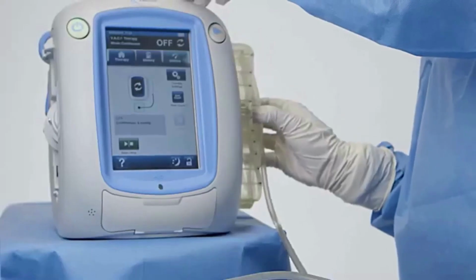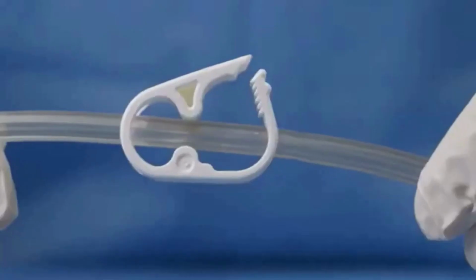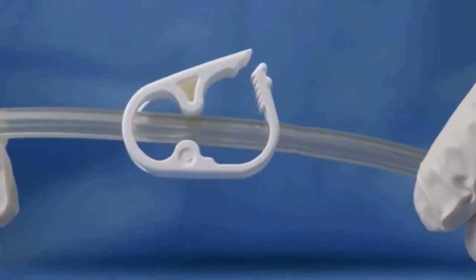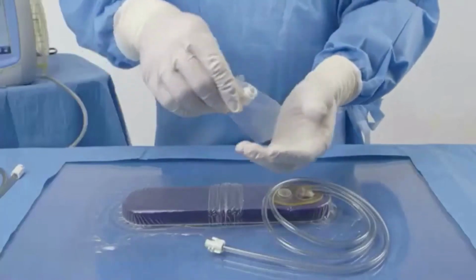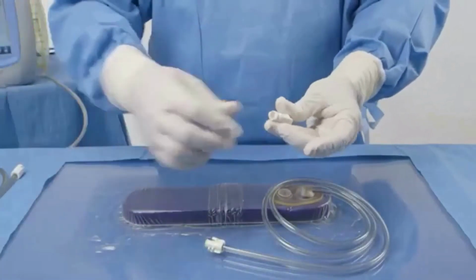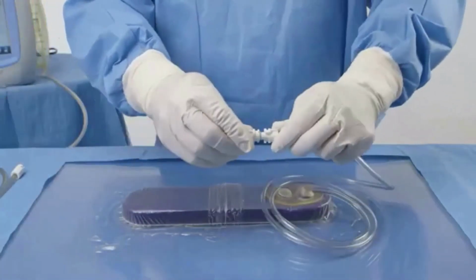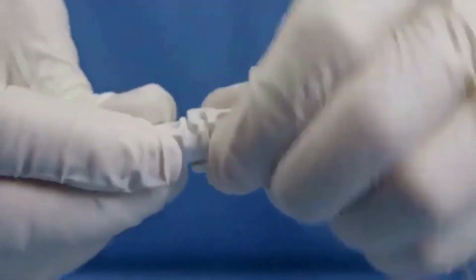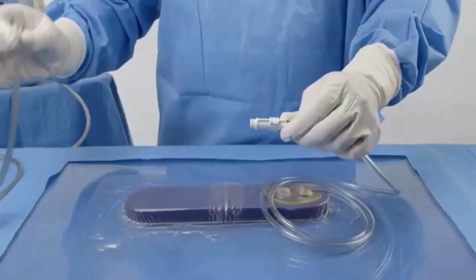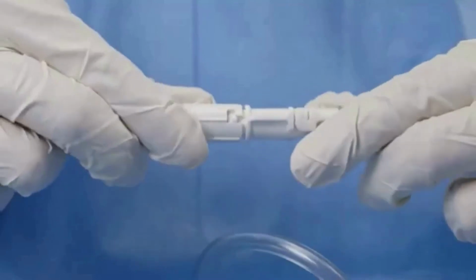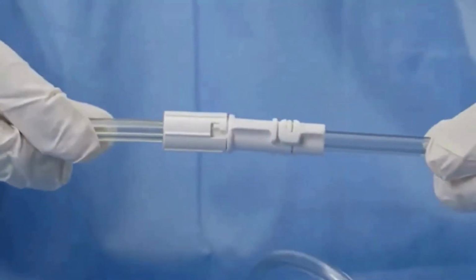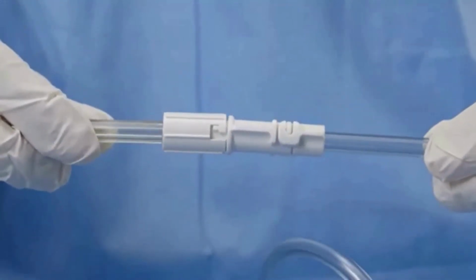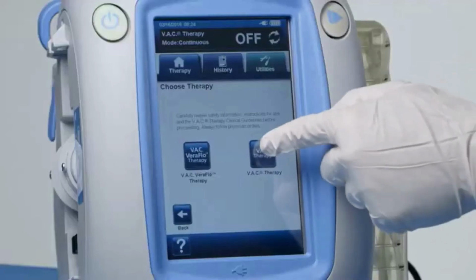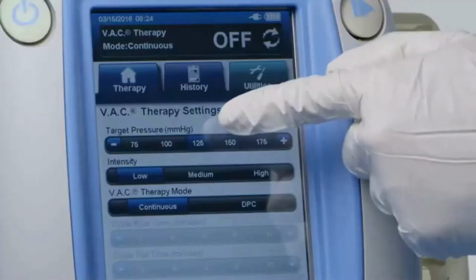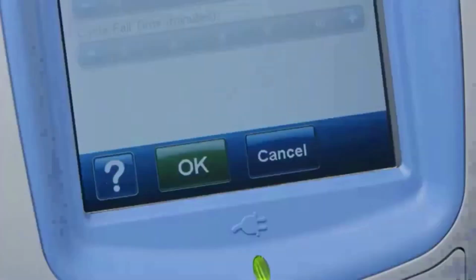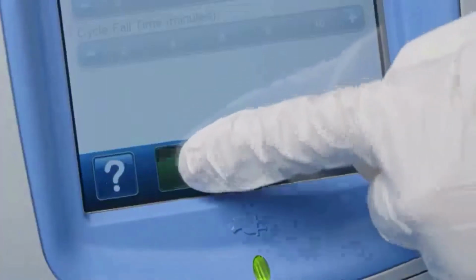Insert and secure the canister into the VAC therapy unit and ensure the clamp on the canister tubing is open. Remove the VAC connector from the plastic bag. Connect the VAC connector to the Prevena dressing tubing by pushing and twisting the connector. Connect the VAC therapy canister tubing to the other end of the VAC connector by pushing and twisting the connectors. Set the pressure to negative 125 mm of mercury continuous mode on the VAC therapy unit. Begin therapy.